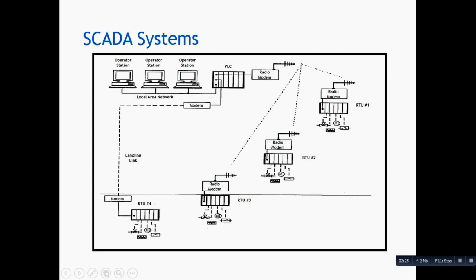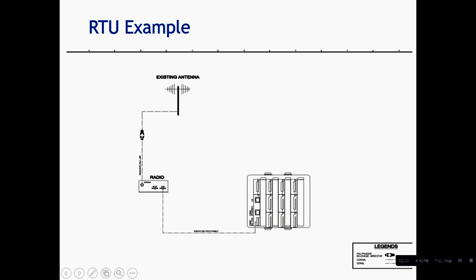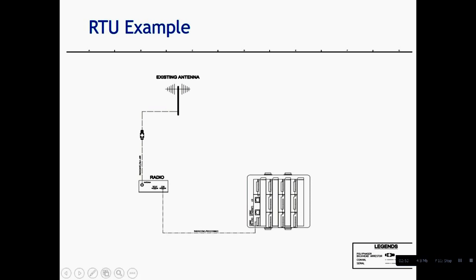Another practical example is this RTU example. Here we have a PLC which is communicating its data on the radio link to the master control room. For example, this is a well site. We have all the parameters of the well, for example, annulus pressure, inlet pressure, tubing pressure, temperature, well status, and all other statuses on this PLC. And we are controlling the HCV through it and well shut-in and start-up commands through it.